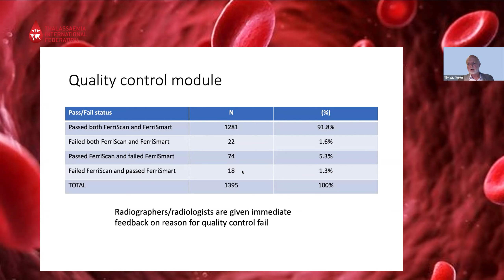And this is then what the correlation looks like between the FerriSmart data on the vertical axis and the FerriScan data on the horizontal axis. The solid line is the line of equivalence. And you can see that there are no, or not a large number of, catastrophic failures, and the sensitivity and specificity for detecting liver iron concentrations above these clinically relevant thresholds of 3, 5, 7, and 15 milligrams of iron per gram dry tissue are all generally in the 90s, apart from the sensitivity for the 15 milligram per gram dry tissue threshold.